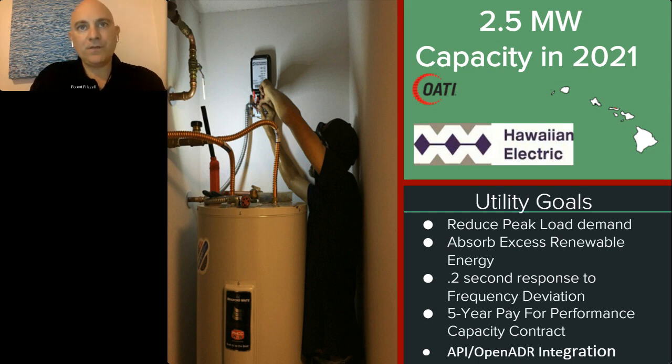And so in Hawaii, our fleet of GIWHs act as a virtual power plant, and they're used to perform grid services deliverables such as a midday load build to take advantage of rooftop solar, an evening load reduction, and then fast frequency response. And fast frequency response has to be activated in 12 cycles. So these services are stacked, and that means that they are all performed on the same day. And we get paid to manage the capacity and the forecasting. And it's really critical that forecasting is correct because there's only a 10% deviation or we get hit with liquidated damages.